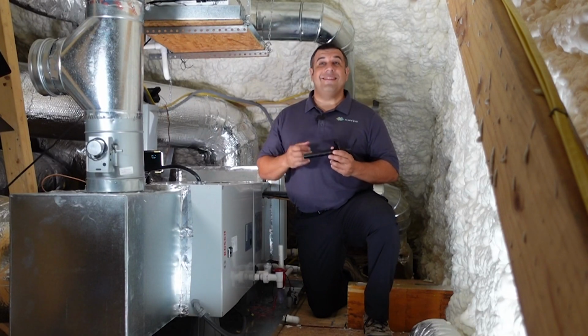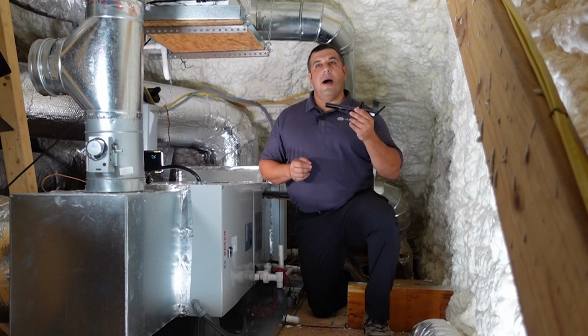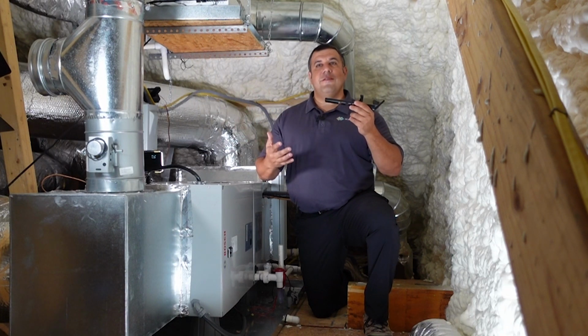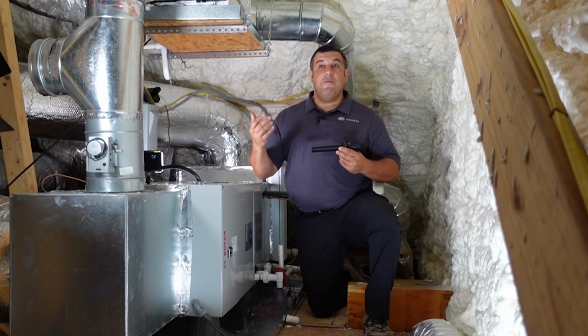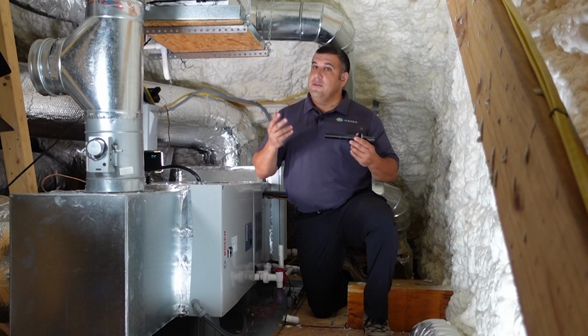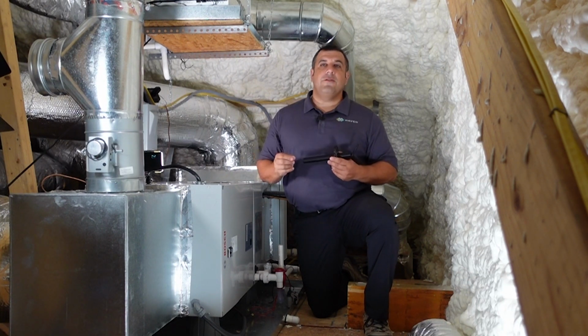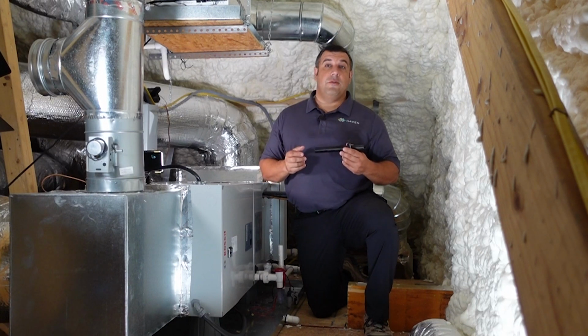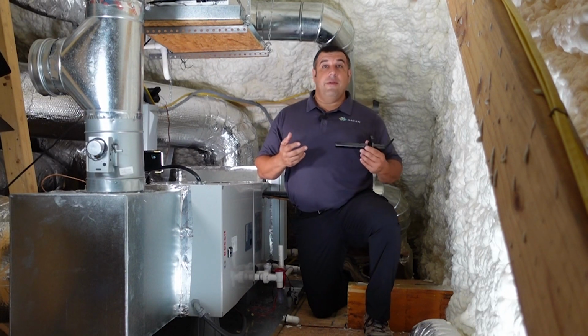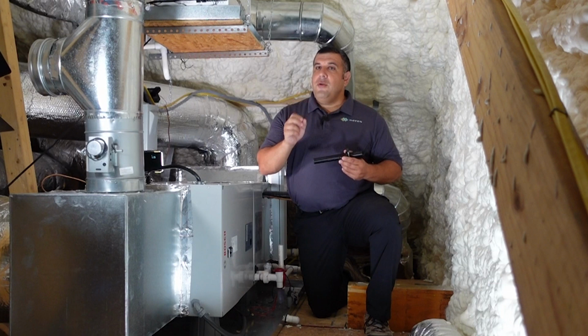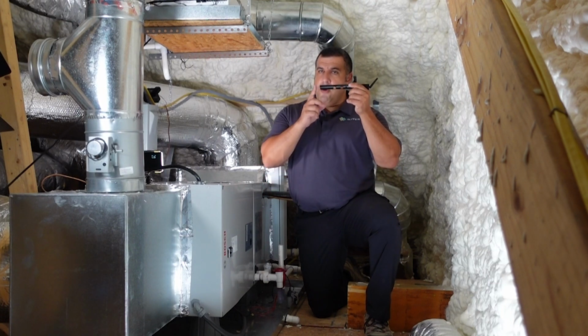Here's what you should know about system compatibility. Since the monitor relies on airflow within the system, it isn't compatible with non-forced air and non-ducted systems such as mini splits. It can be installed in other configurations such as the return of an ERV, HRV, or dehumidifier, as long as you have at least 8 inches of depth for the probe.